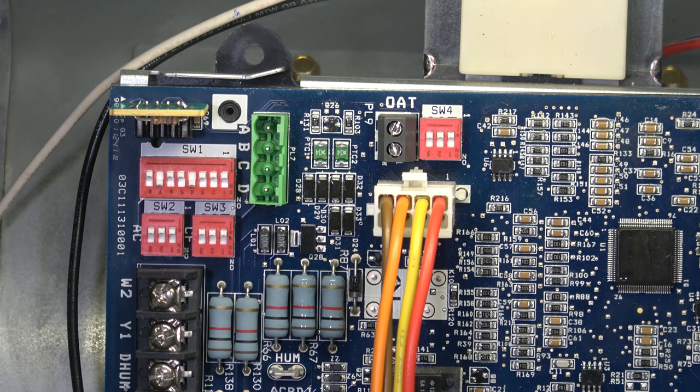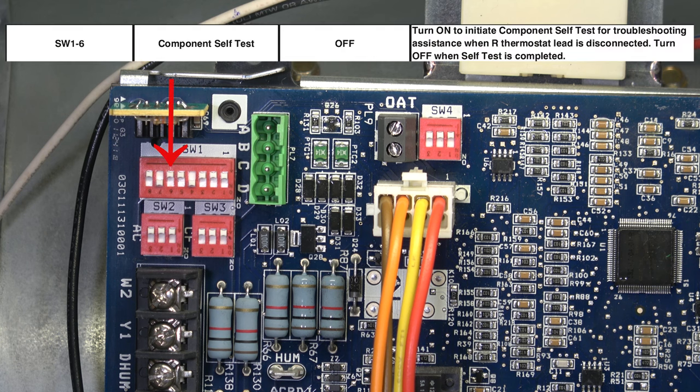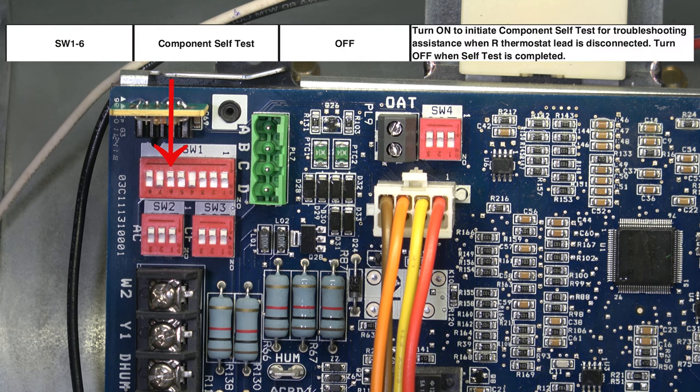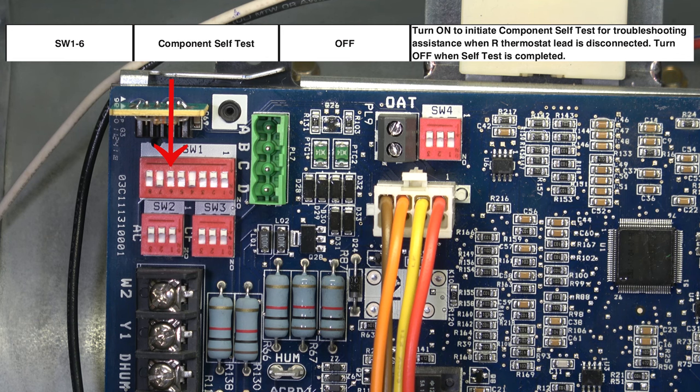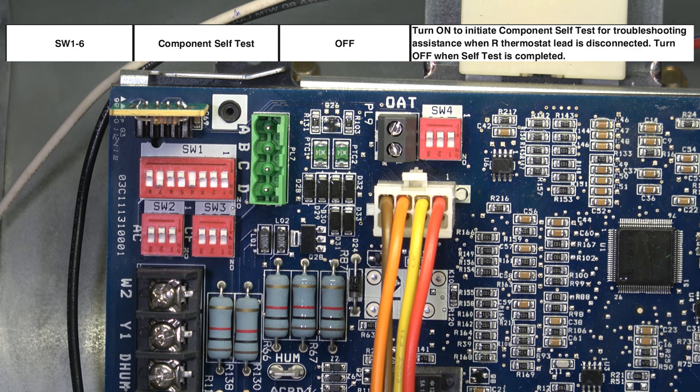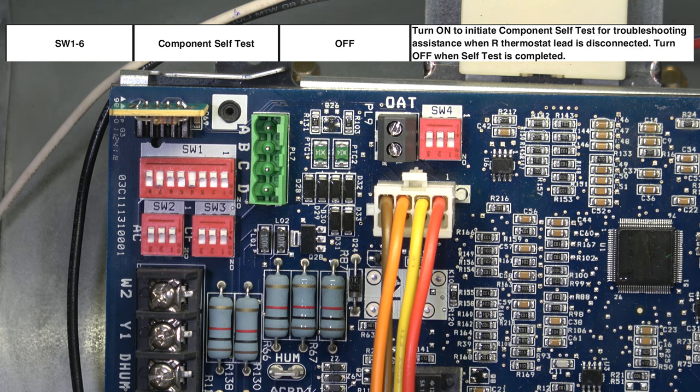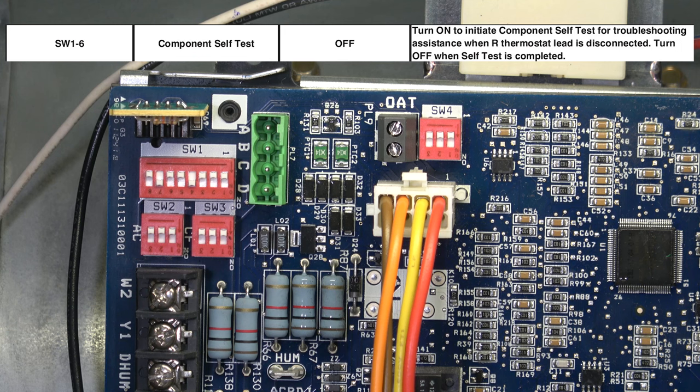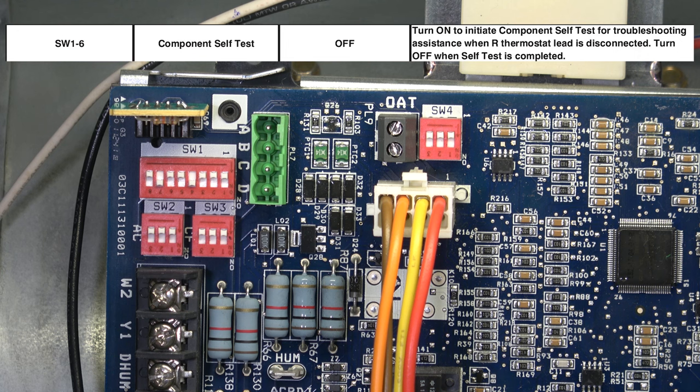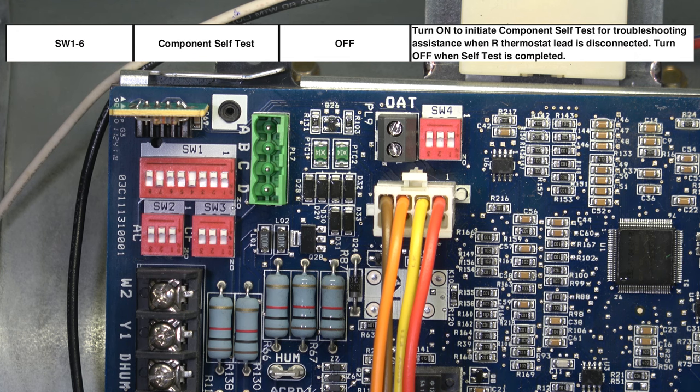Moving to the next switch, SW1 number six is the component self-test. This switch is normally off. If you turn that switch to on, it will initiate the component self-test for troubleshooting. When that is on, it runs the system through a check for all components to see what's operational and where there may be an issue.